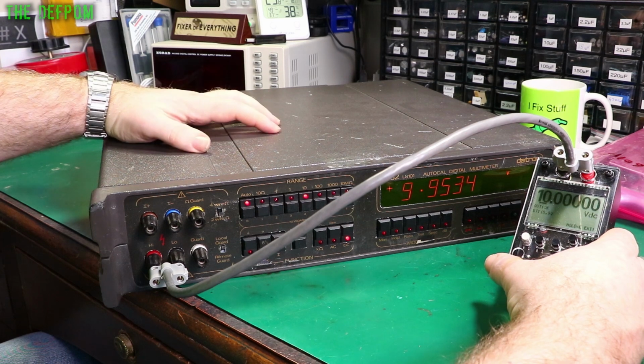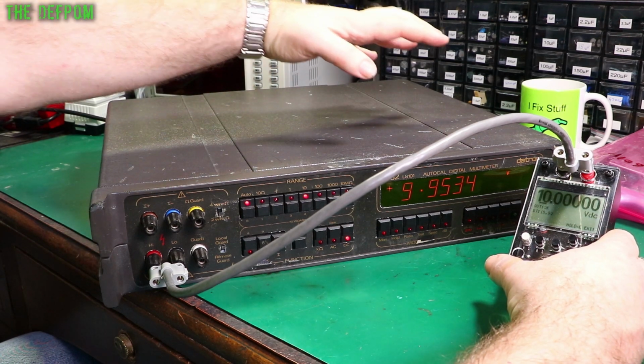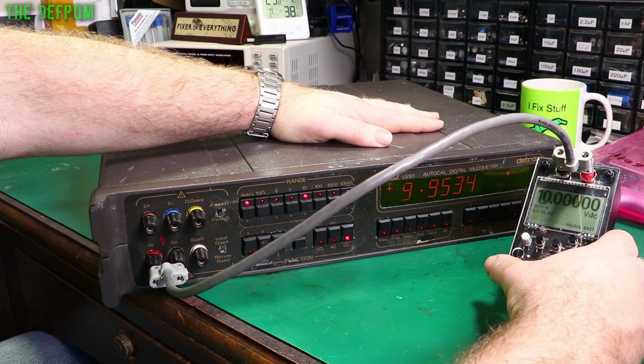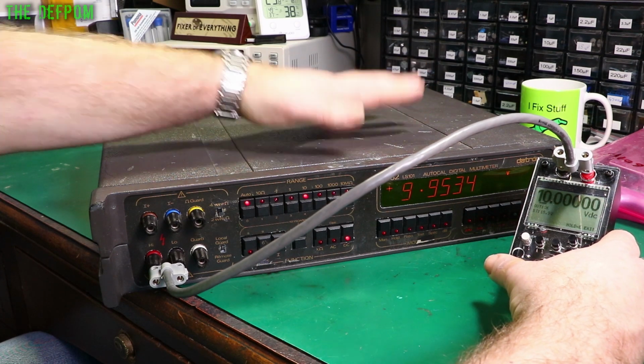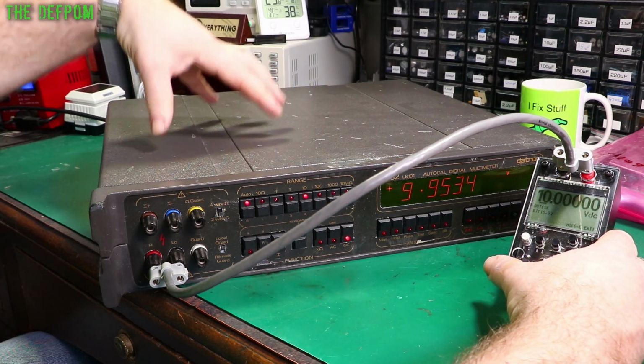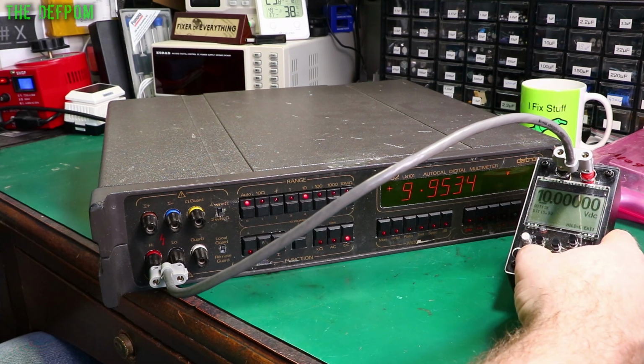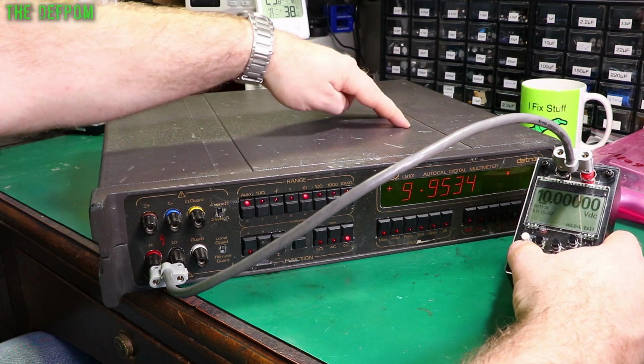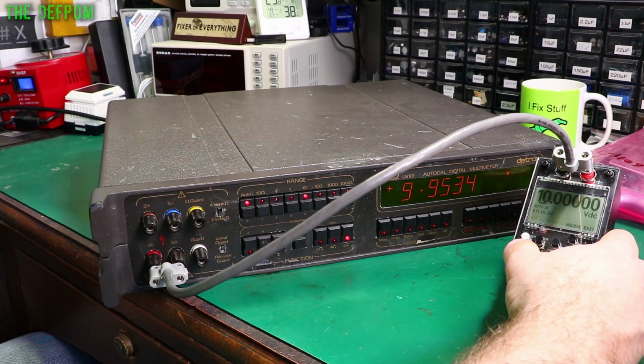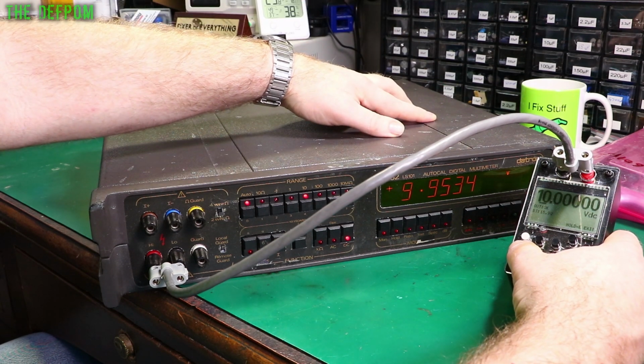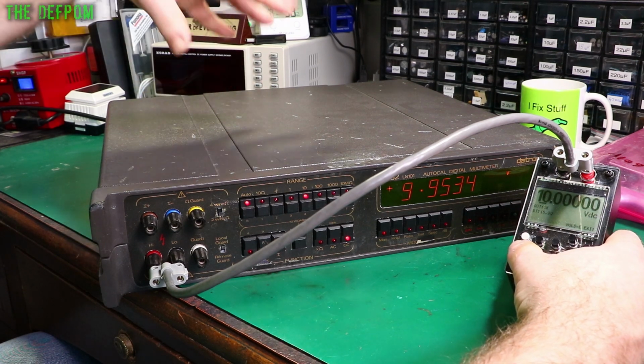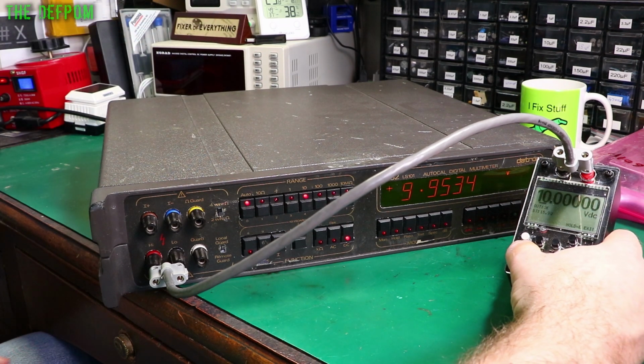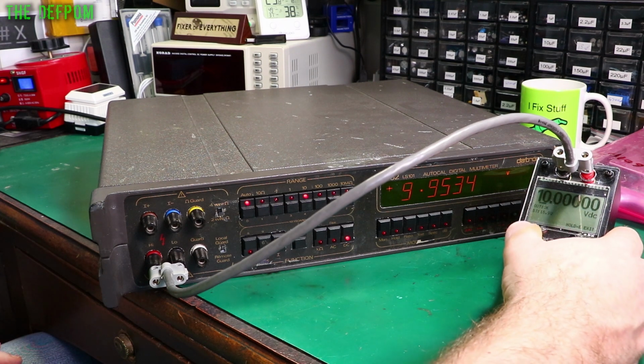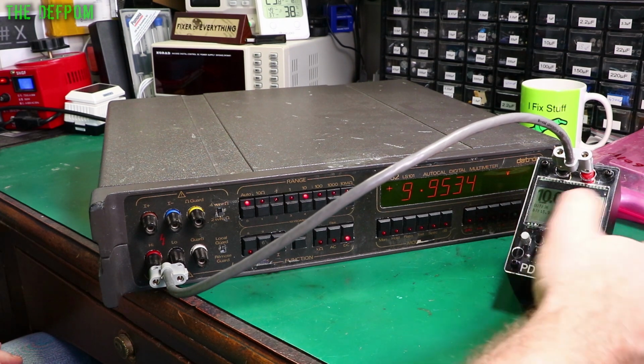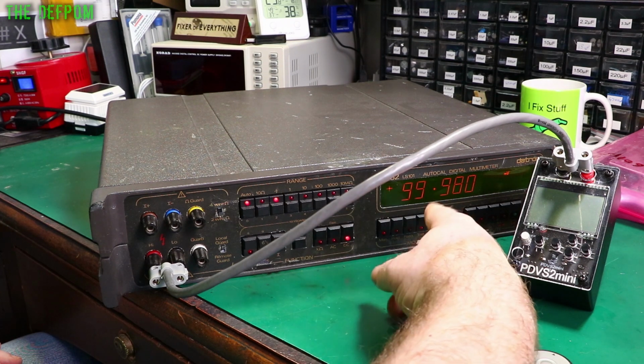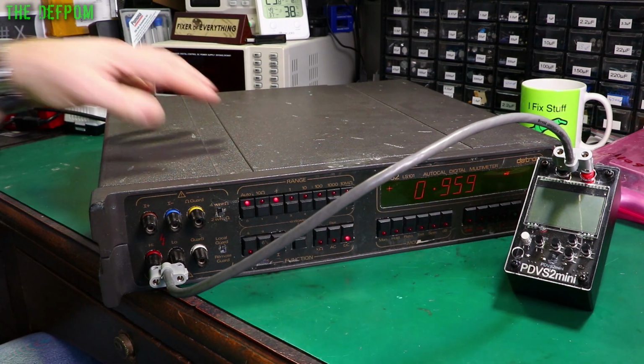Now if I can just do the DC board only, maybe the digital calibration is still okay. Right, and that may mean that the rest of the calibration points are still good. If I just do this board, that might be all I have to do. There's a couple of references on this board you have to do as well. I can do those, a couple of adjustments, not much. So I'll do those digital adjustments first, then we'll go over and do the digital board, and this DC board, and then we'll see how everything else looks after that. I do remember the resistance measurements and the AC measurements were off as well. I do remember that much, so that's what we're going to tackle.